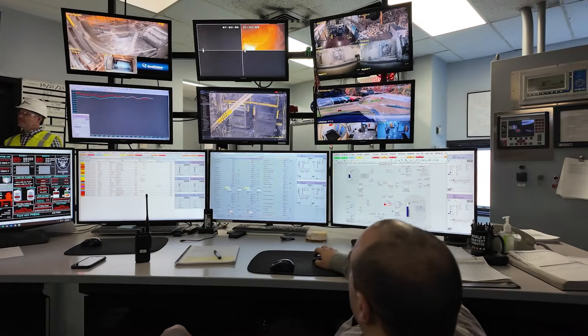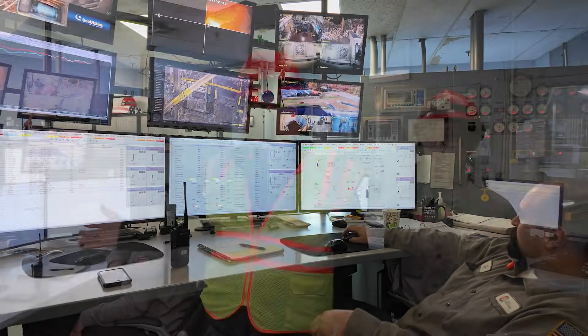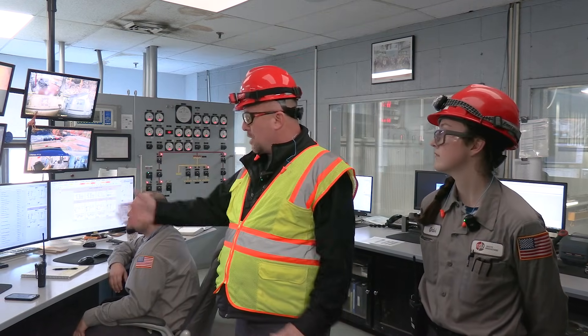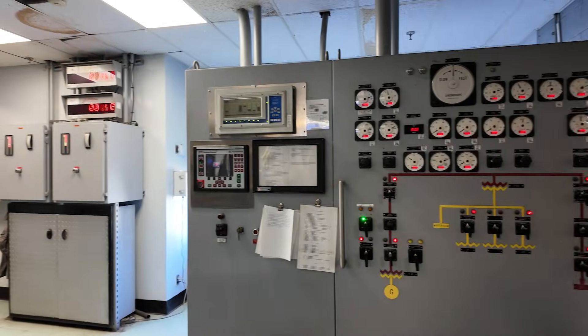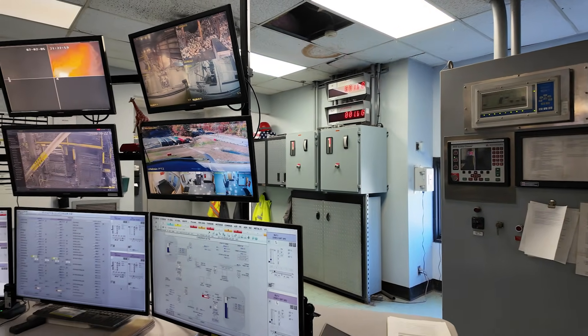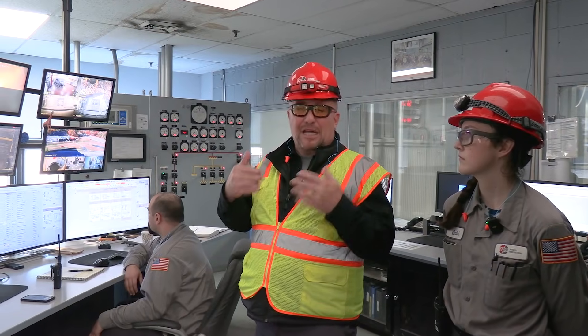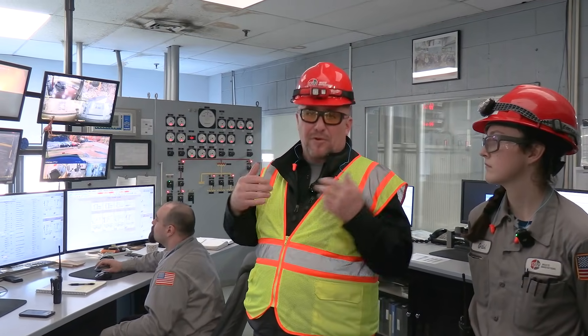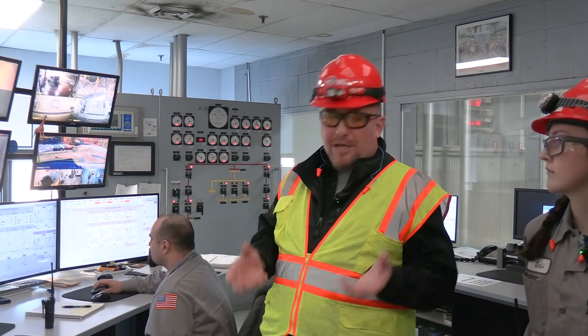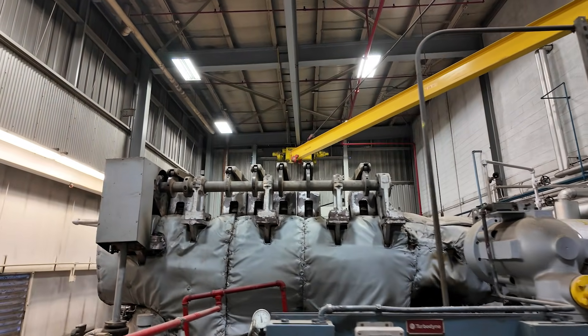This is the control room, where the boilers' steam load is controlled. Our control operator is monitoring emissions — NOx, SO2 gases, CO, and oxygen levels. He can increase the ram speed to feed more refuse into the fires, slow it down, or increase the air on both boilers, feeding into a giant steam header.